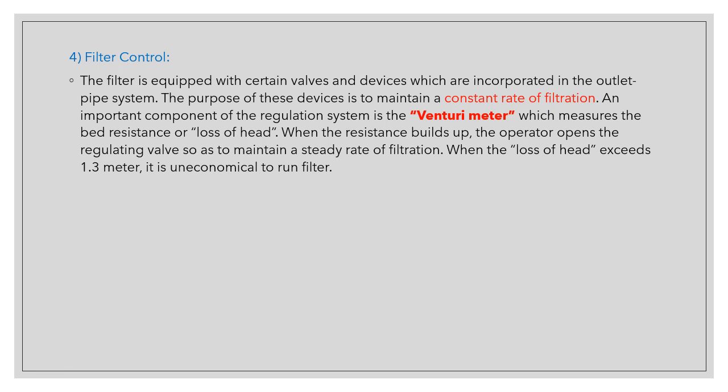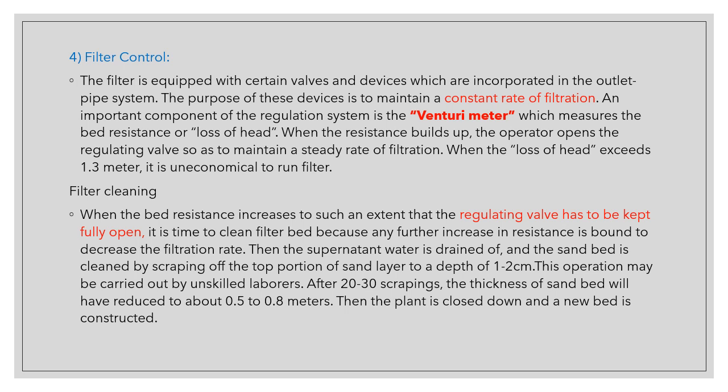What do we do then? We actually are going to wash the filter. This is known as filter cleaning. When the bed resistance increases to such an extent that the regulating valve has to be kept fully open, then it is time to clean the filter bed, because any further increase in the resistance is actually bound to decrease the filtration rate. So the supernatant water is going to be drained off.